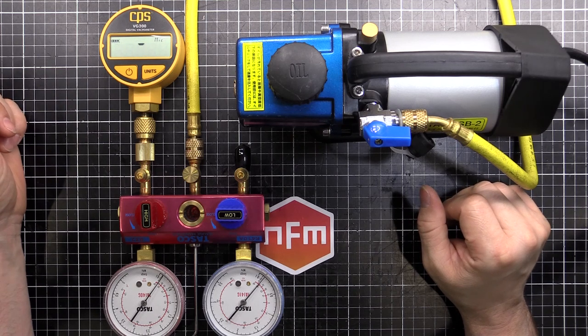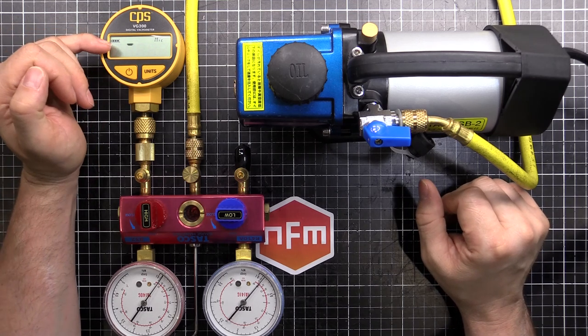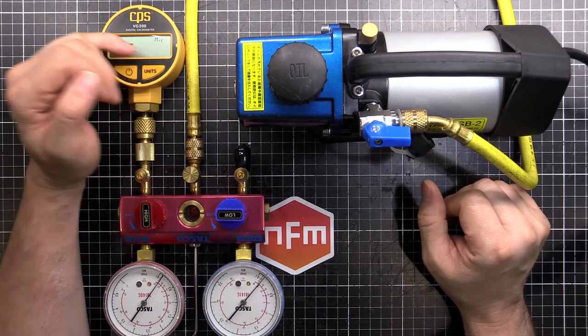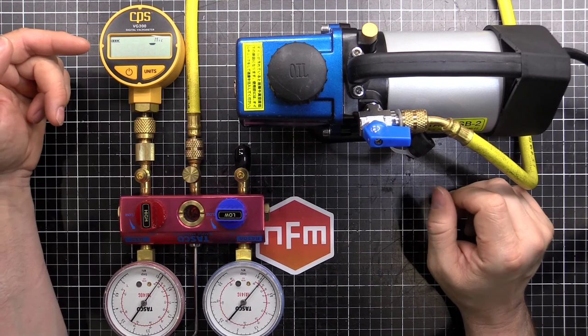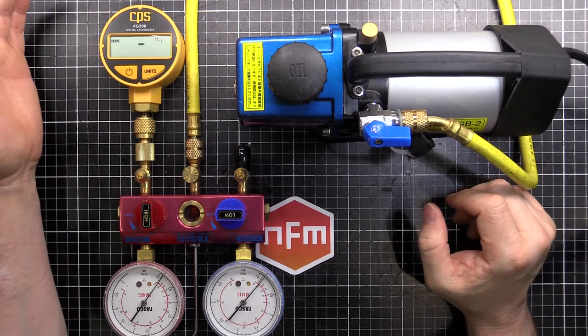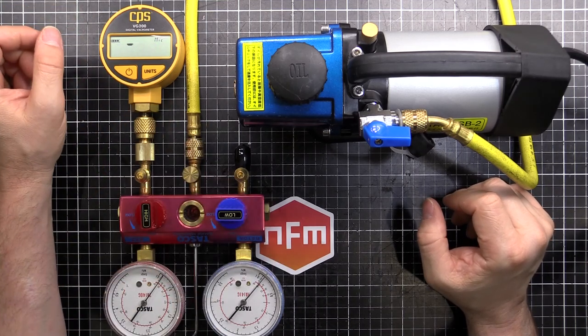And we've got a flashing cursor. This cursor basically means that the pressure is too high for it to read. As the pressure drops, that cursor will drop down and then to the bottom of the figure-eight segments in the display. And then it will start showing the actual number. It's just too big. And it's essentially meaningless at this pressure. You use a different gauge for doing pressures at atmospheric levels.